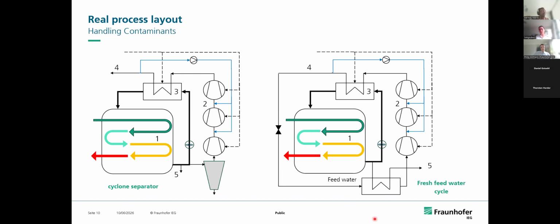Yes, we can talk about that. Here we used this to avoid dirt or particles, but this is a closed loop architecture. You could use another refrigerant, for example a hydrocarbon or an HFO. Generally, you would achieve lower costs, especially for HFOs, when you don't have to think about the hazard class and ATEX precautions, but you would generally achieve lower COPs. Why is that? Water has the highest critical temperature, and in this very high temperature range, it is the refrigerant of choice when it comes to COP. So you would have significantly lower COPs due to the higher temperature range where you operate the process. I would assume that for, let's say, 80 to 90% of the cases I can think about, water would be the best selection.